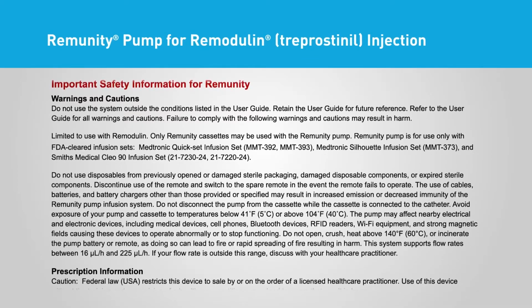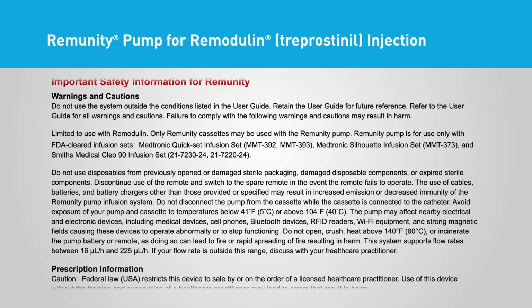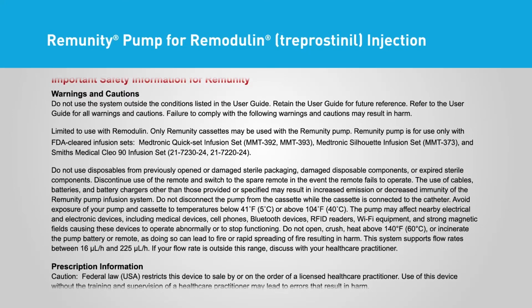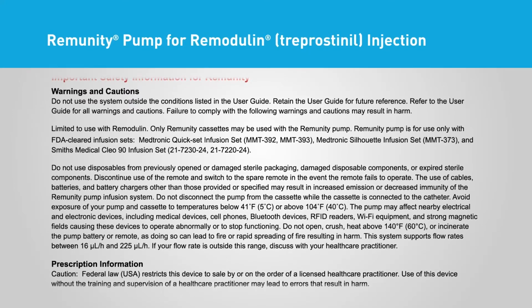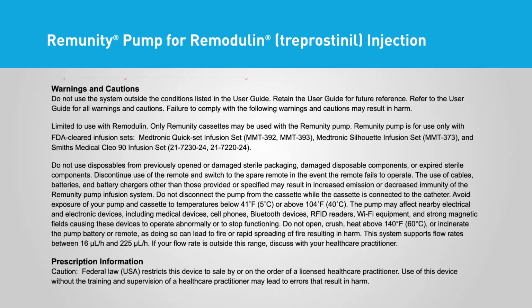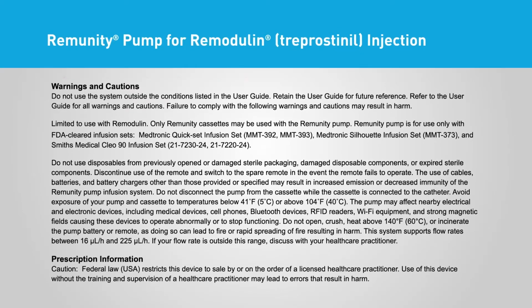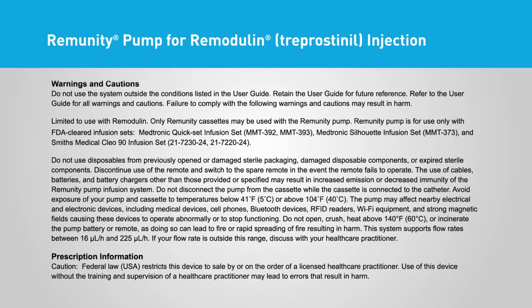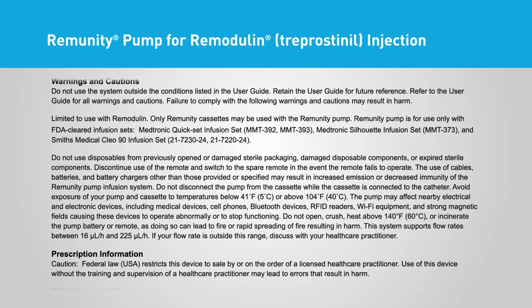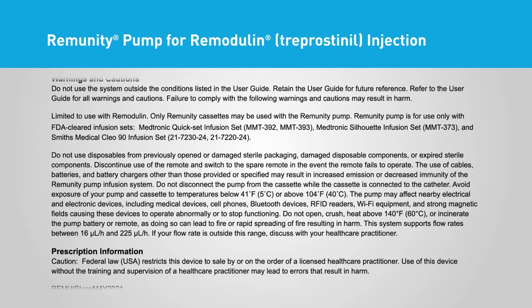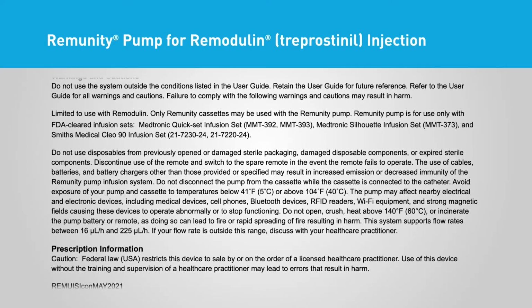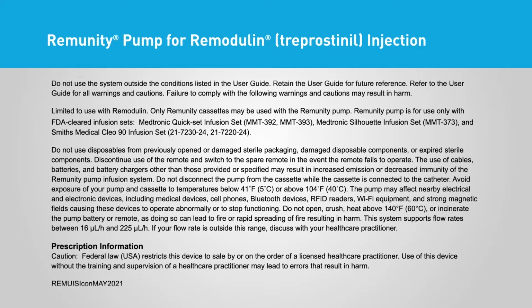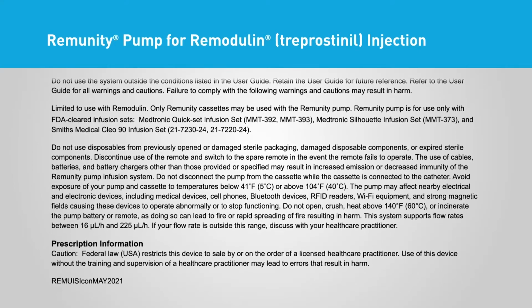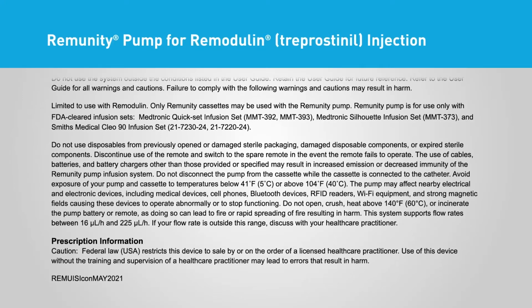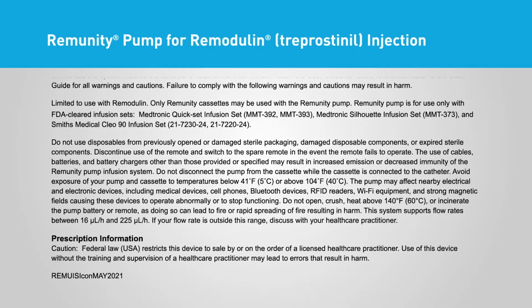Discontinue use of the remote and switch to the spare remote in the event the remote fails to operate. The use of cables, batteries, and battery chargers other than those provided or specified may result in increased emission or decreased immunity of the Remunity Pump infusion system. Do not disconnect the pump from the cassette while the cassette is connected to the catheter. Avoid exposure of your pump and cassette to temperatures below 41 degrees Fahrenheit, 5 degrees Celsius, or above 104 degrees Fahrenheit, 40 degrees Celsius.